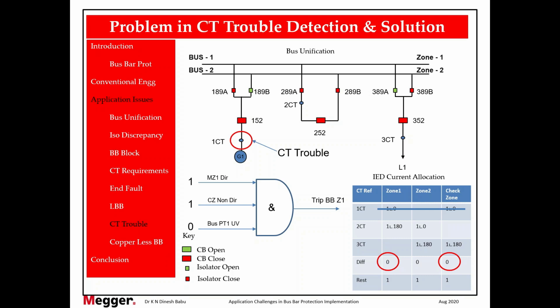Because in this example, we have considered only 2 bays. But in the majority of cases, many bays would be there. Just because one current is not there, it doesn't mean the directional principle will get satisfied. There may be another 5 to 10 bays. Out of these 5 to 10 bays, several incoming and several outgoing bays would be there. So during a fault, for the directional feature to pick up, all the current should flow in the same direction. Only then will directional pick up. So in this example, we have considered the worst case where only 2 feeders are there. So directional has picked up.